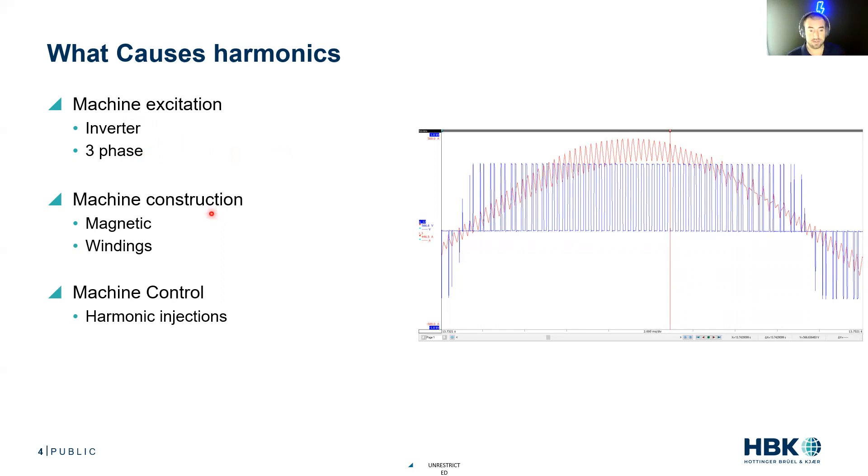We also have machine construction. There's the magnetic construction, which is not going to be perfectly sinusoidal, and anything that's not perfectly sinusoidal is going to cause a harmonic element. And the winding distribution - we can wind the machine to try to even out that harmonic content, but we're never going to do it perfectly because there's no such thing as a perfect sine wave.